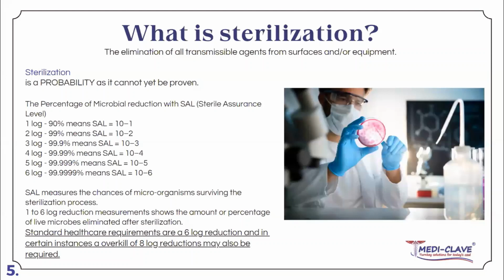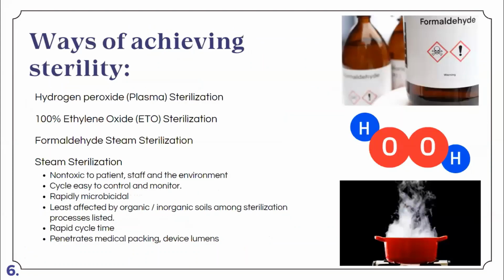There are many ways of achieving sterility, like hydrogen peroxide, ethylene oxide, formaldehyde steam sterilization, and normal steam sterilization. This will be the one that we are focusing on today, as autoclaves are associated with steam sterilization. They use steam as a sterilant for the equipment inside. So steam sterilization benefits are they are non-toxic to patients, staff, and environment. Their cycles are easily controlled and monitored. They have rapid cycle times, and they penetrate deeply into medical packs as well as your device lumens.